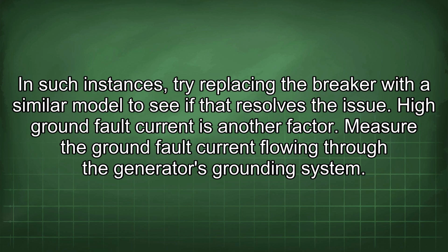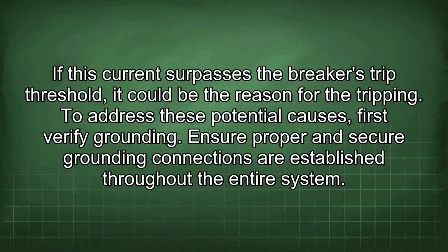High ground fault current is another factor. Measure the ground fault current flowing through the generator's grounding system. If this current surpasses the breaker's trip threshold, it could be the reason for the tripping. To address these potential causes, first verify grounding. Ensure proper and secure grounding connections are established throughout the entire system.